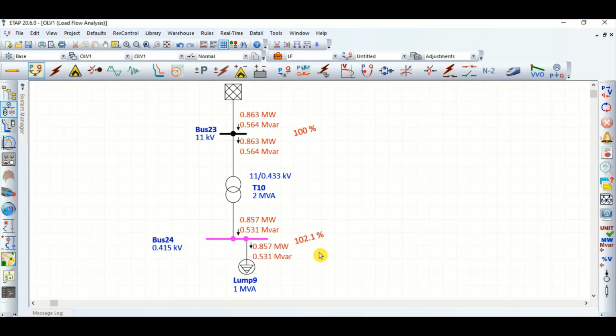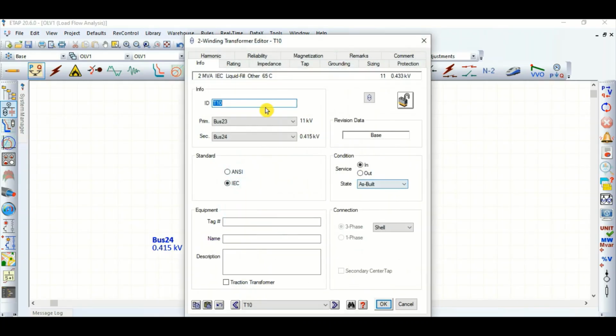So definitely there is an impact. We should not ignore this whenever we are modeling in ETAP. Based on the transformer manufacturer data sheet, we have to consider whether the transformer secondary side no load voltage is the bus voltage, meaning 415 volt, or 433 volt, because it will have an impact. It was 97.8%. Now it is more than 102%. This is one aspect.